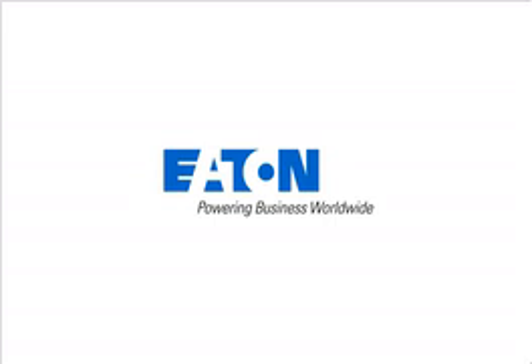Are UPSs used for other things other than lighting, such as pressurization fans, etc.? It's awfully tempting to do that, I know, but the latest versions of the fire code say that if you're going to use a UPS for emergency lighting, then that UPS must serve no other purpose. So I can't take my giant data center UPS, for example, and use it for emergency lighting, or my mechanical system support UPS system and use it for emergency lighting. So if I'm going to use a UPS, it has to be a dedicated UPS and only for lighting backup.